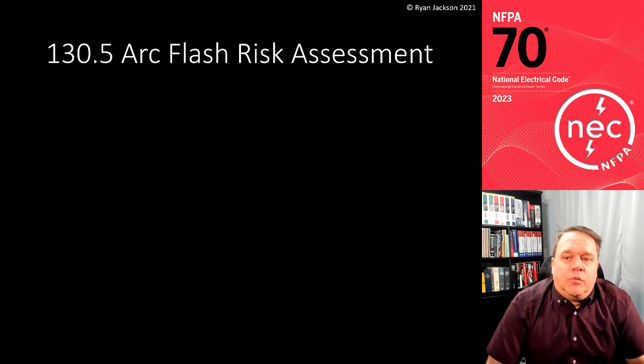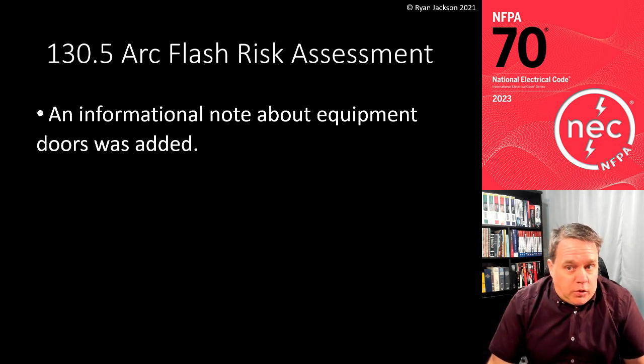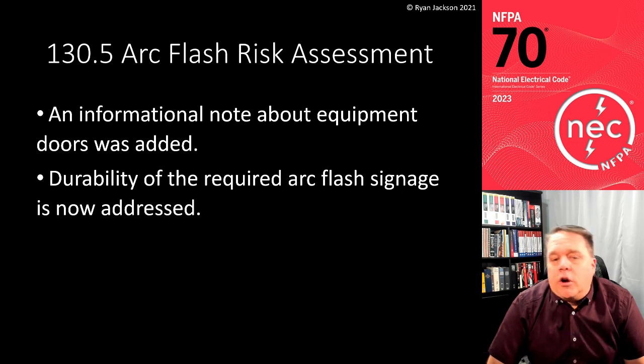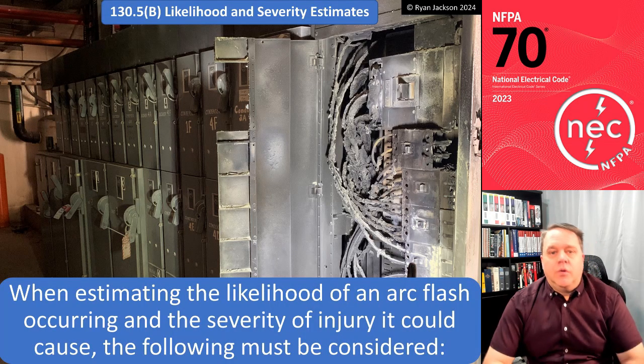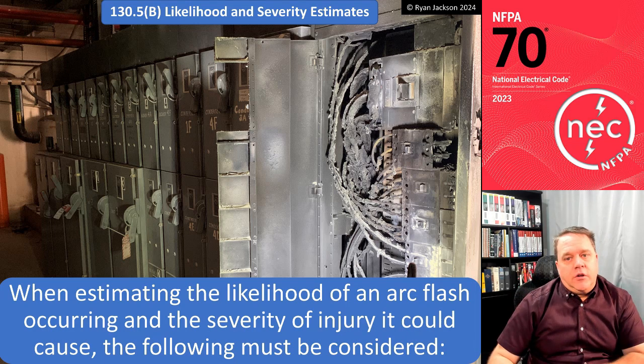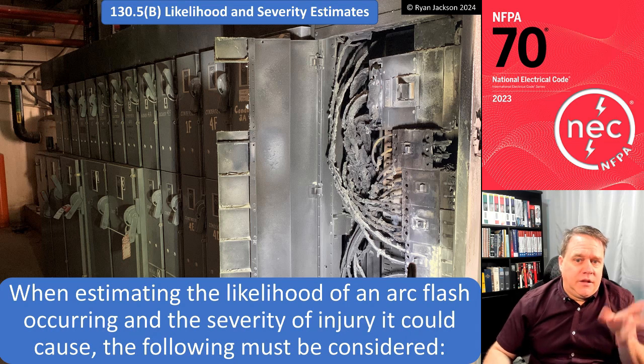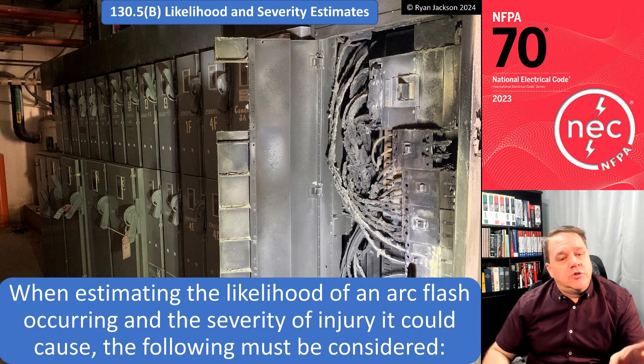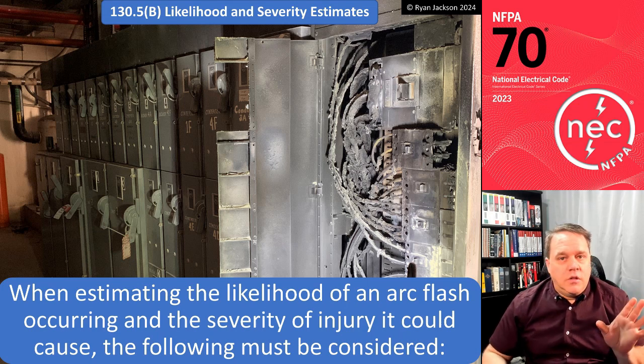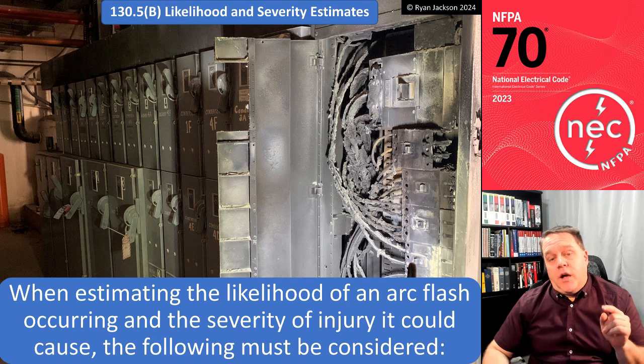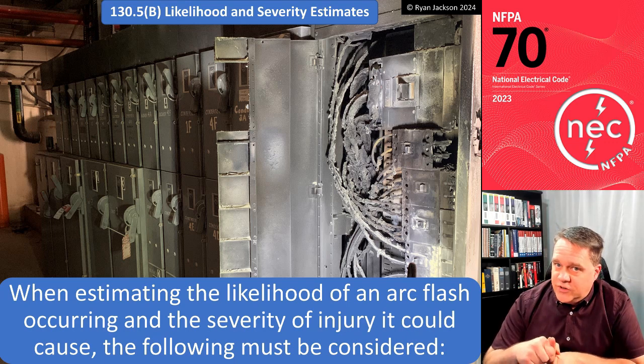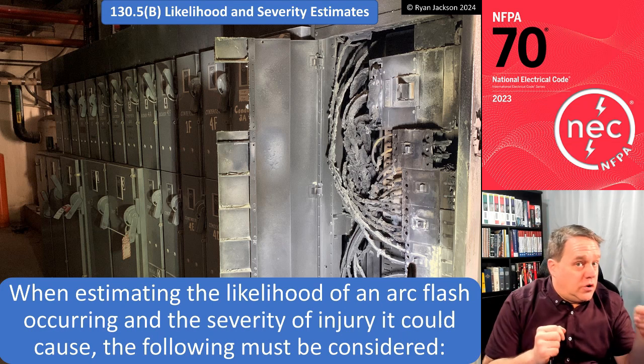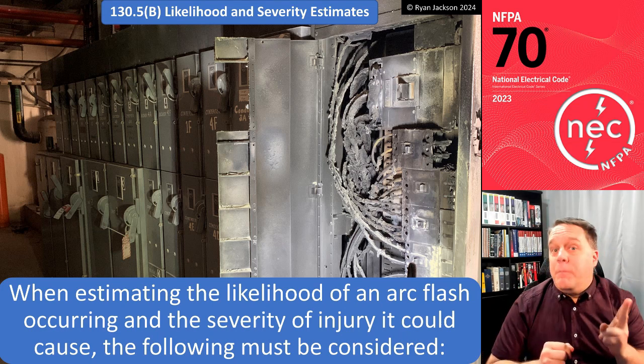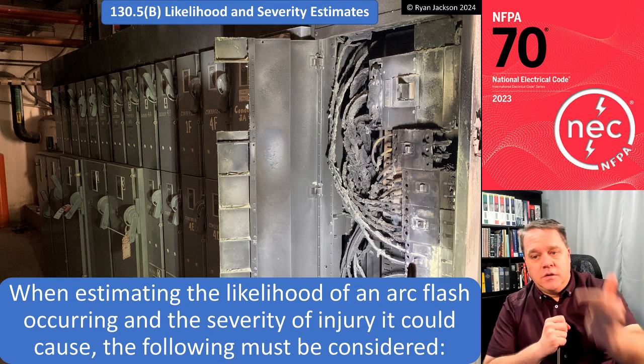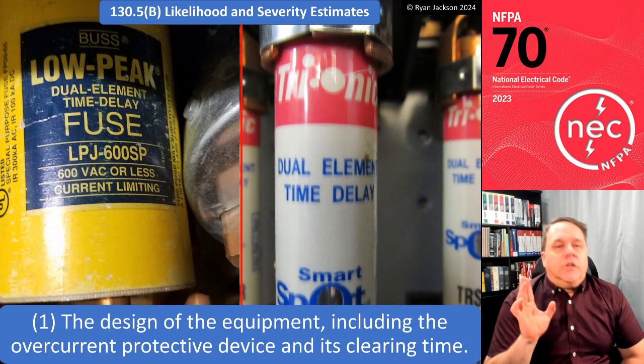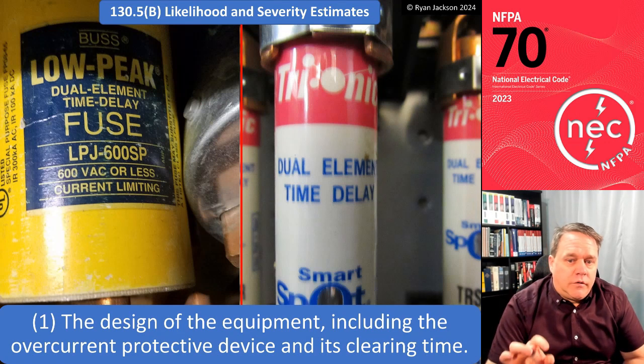130.5, arc flash risk assessment. An informational note about equipment doors was added, and the durability of the required arc flash signage is now addressed. All right, so 130.5(B), likelihood and severity estimates. When you're estimating the likelihood of an arc flash occurring and the severity of injury it could cause, then you need to consider the following items. And really, that's the name of the game, right? You need to do a shock risk assessment. You need to do an arc flash risk assessment. Both of those are determining the likelihood of something bad happening and how bad it would be if it did happen. Likelihood, severity.